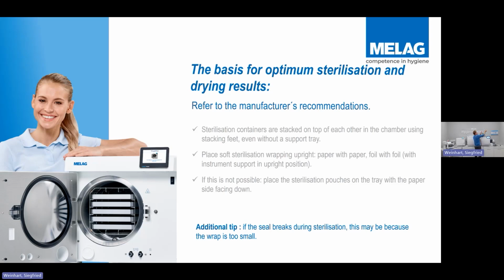So make sure we use the correct size pouch for the instruments we're loading in there. Don't overload the pouches. Don't have instruments multi-stacked on top of each other within the pouch as well. Okay, because again, if you've got multiple instruments bunched up on top of each other, the steam's not going to get around. The steam's not going to move those instruments for you. So it needs to be able to get into contact with the surfaces. The steam will only sterilize surfaces it gets into contact with. If it can't get in contact with the surface, it can't sterilize the surface.